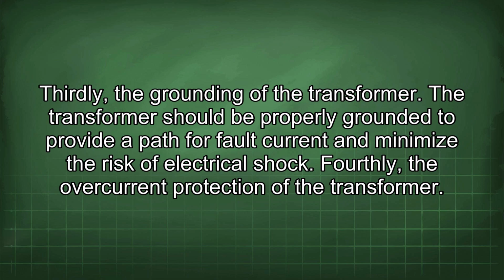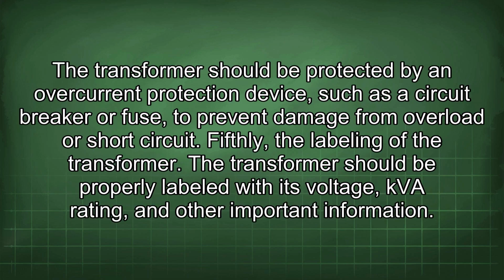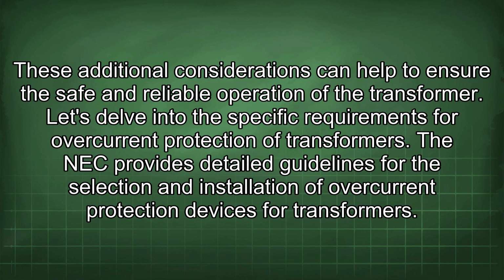Fourthly, the overcurrent protection of the transformer. The transformer should be protected by an overcurrent protection device such as a circuit breaker or fuse to prevent damage from overload or short circuit. Fifthly, the labeling of the transformer. The transformer should be properly labeled with its voltage, kVA rating, and other important information. These additional considerations can help to ensure the safe and reliable operation of the transformer. Let's delve into the specific requirements for overcurrent protection of transformers.